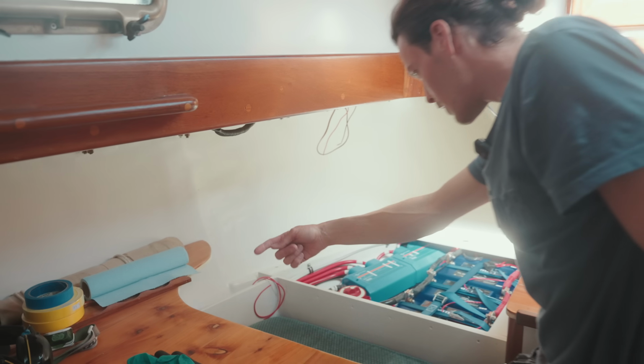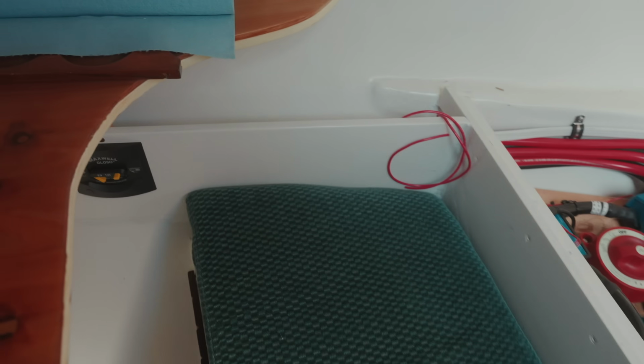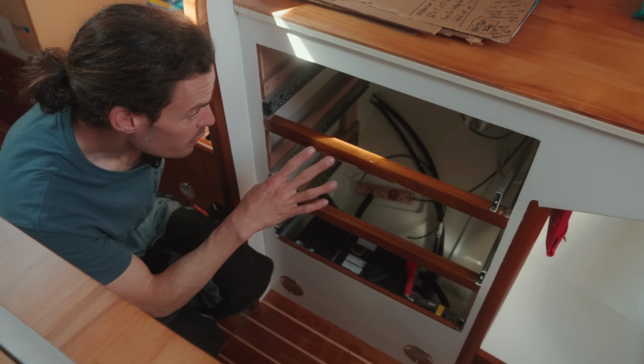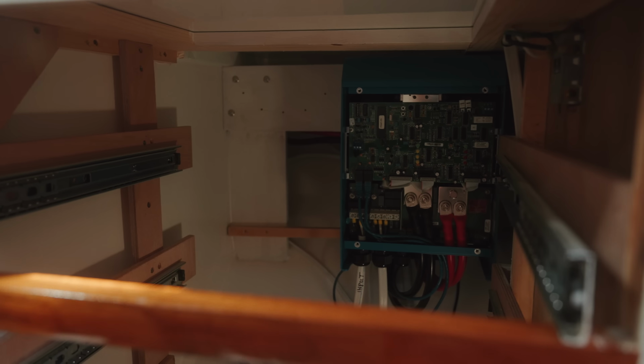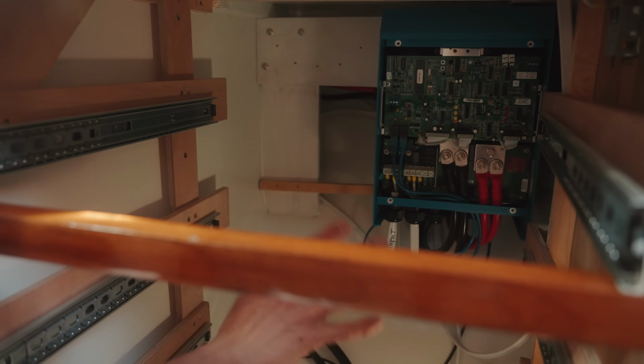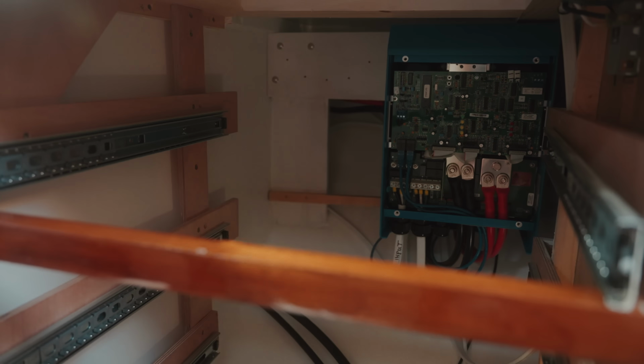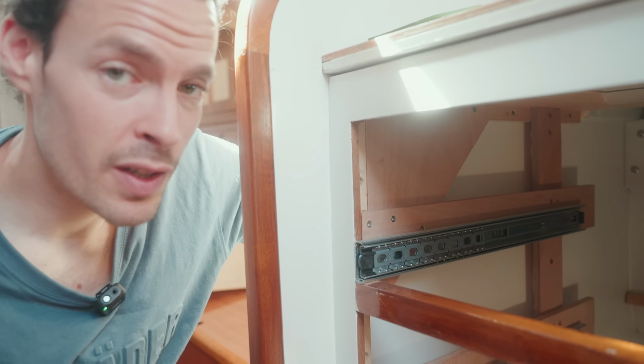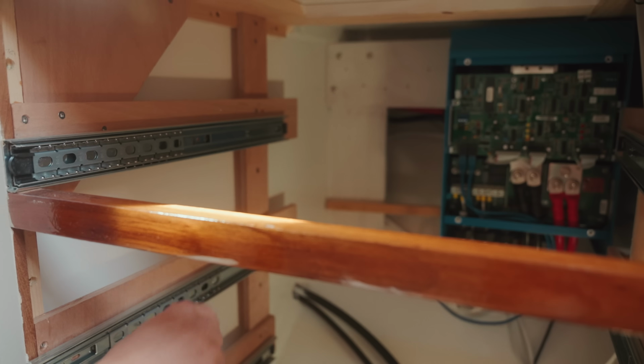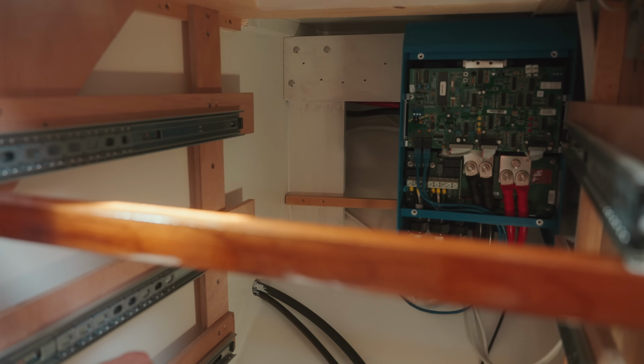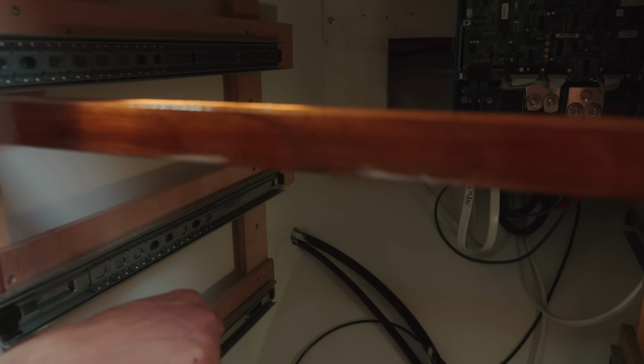I made this little channel for all the wires to go through, it will still get a lid. Over here we have the inverter charger, it's a Victron Multiplus 12-3000. I've wired in, for now, the AC to feed the inverter charger. We are still waiting on an isolation transformer, there's the perfect spot for it right there, so installation is just waiting to happen. Everything is ready. Later we will feed the isolation transformer directly, and from the isolation transformer output, that will feed the inverter charger, so I'll just have to swap one connection, famous last words.